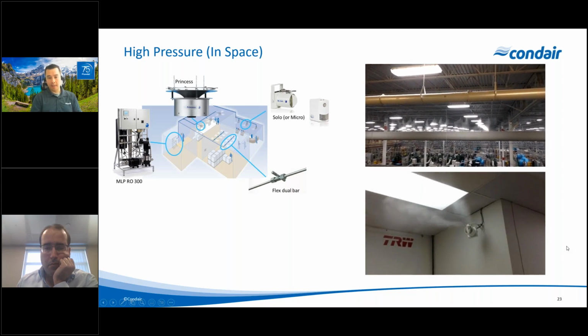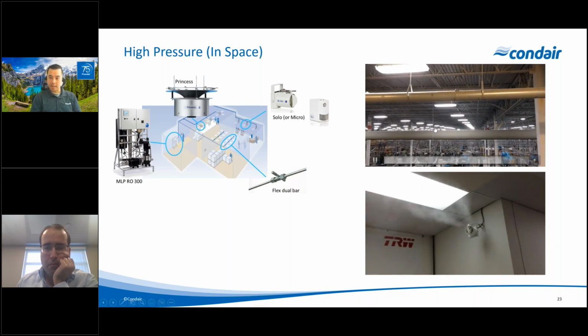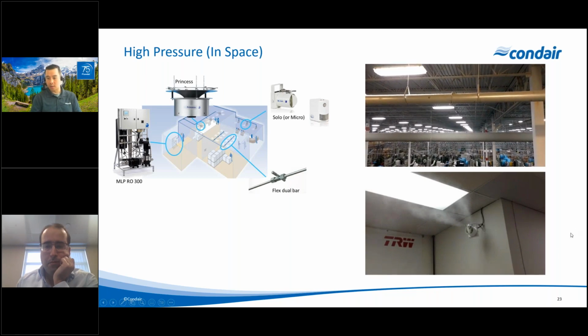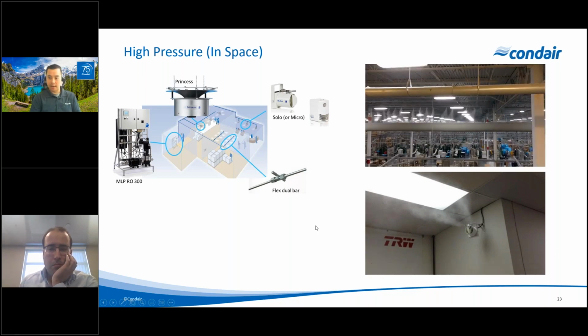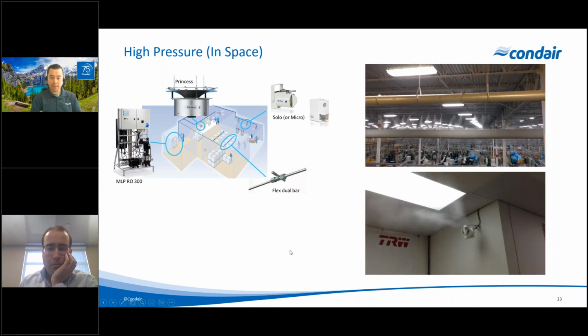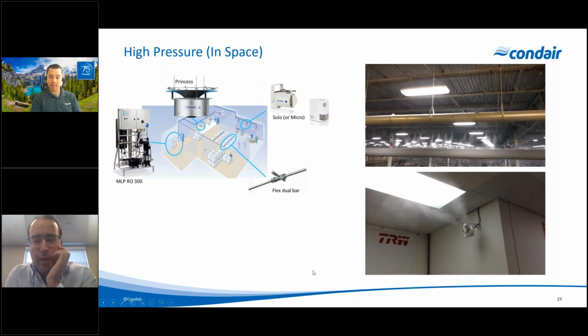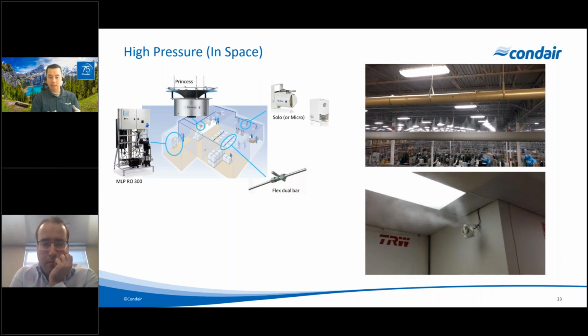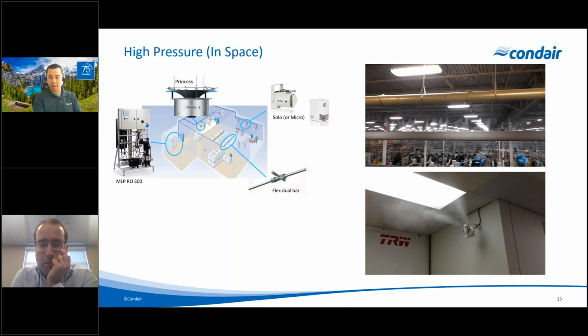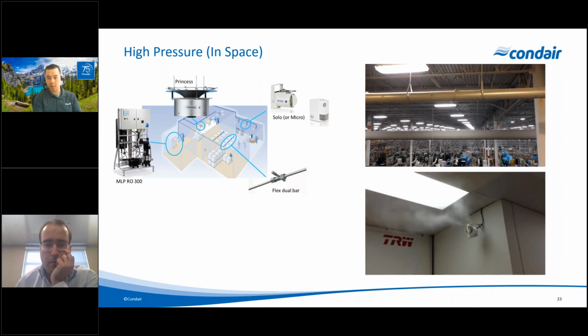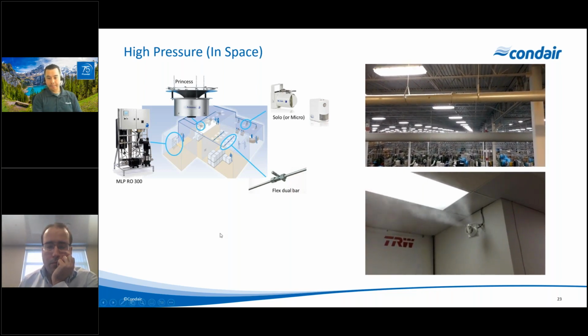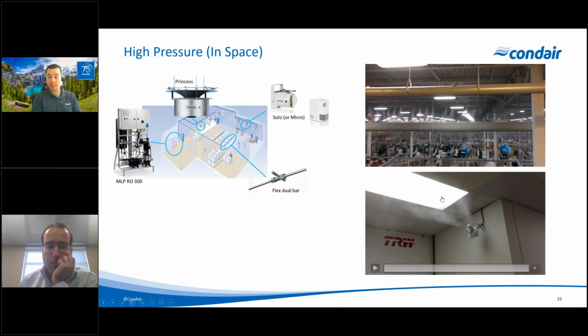Now, the nice thing about the high pressure in-space systems is we can do multiple zones as well. So if you have a manufacturing zone and you have an office space and you want to humidify those, each with different set points and control each one individually, we can do that with a single pump station, provided the capacity is within the capacities of that pump station itself. But the nice thing is we can mix and match different technologies or different zones with the single system.